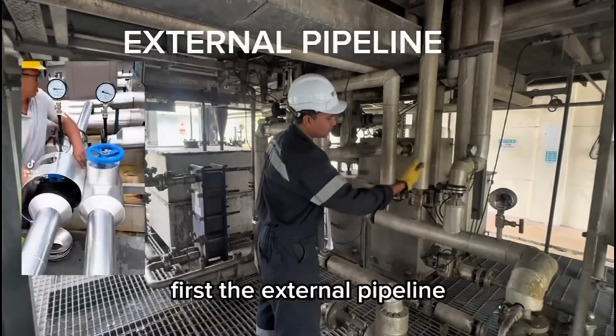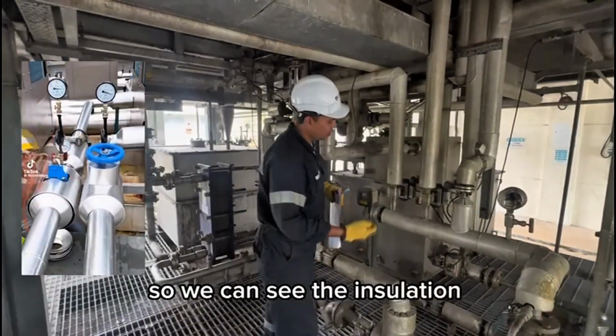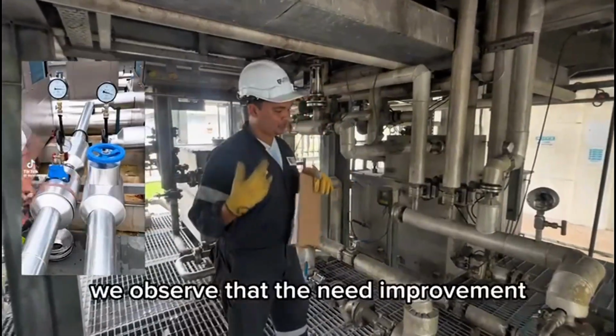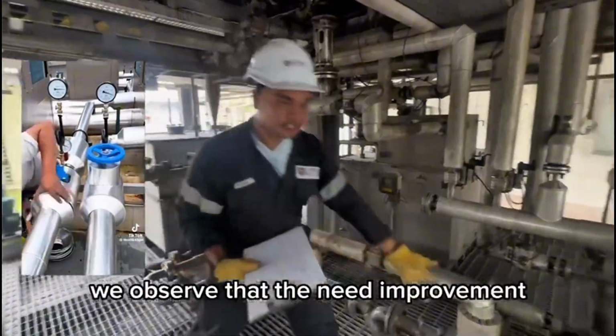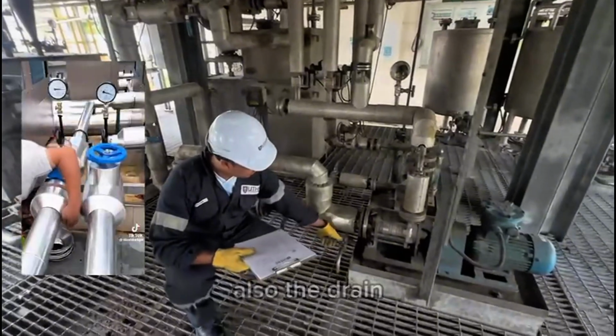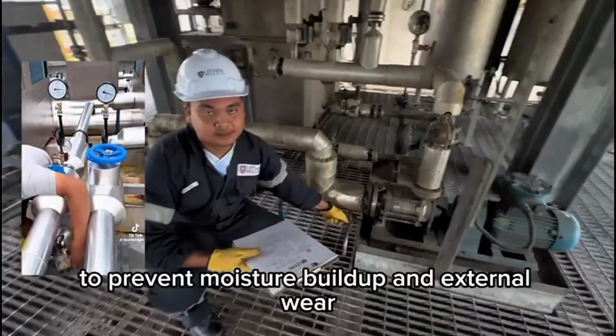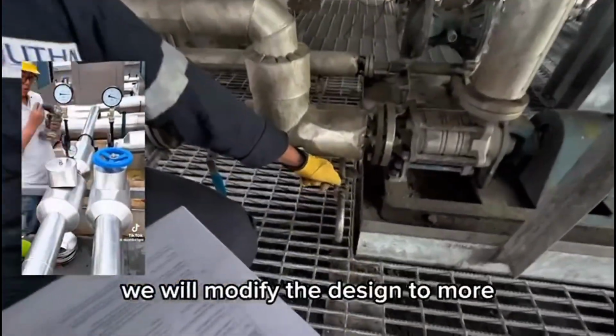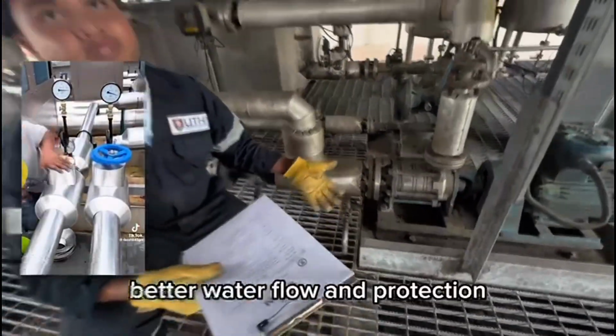First, the external pipeline. So we can see the insulation design. We observe that the design needs improvement, also the drain, to prevent moisture build up and external wear. We will modify the design for better water flow and protection.